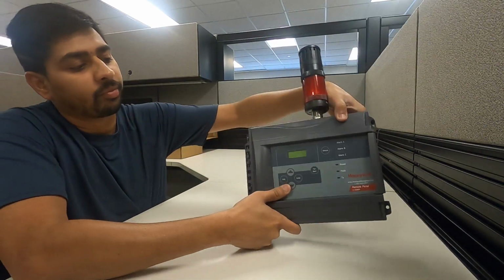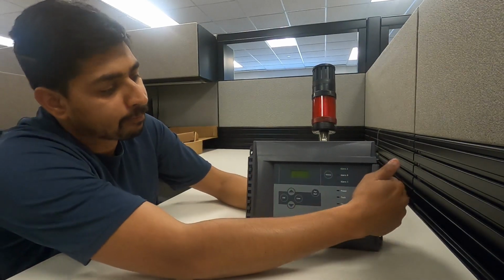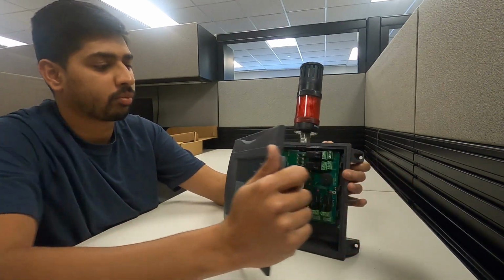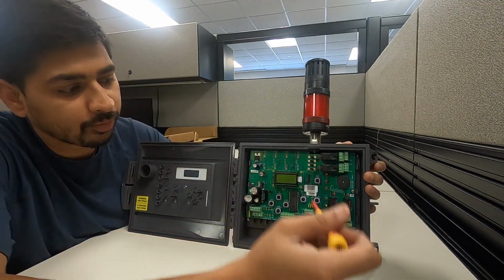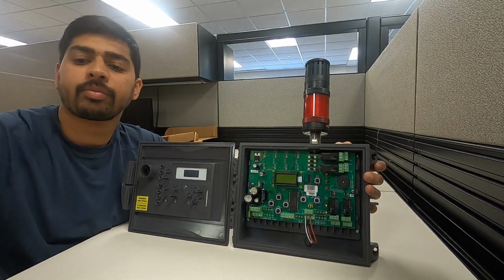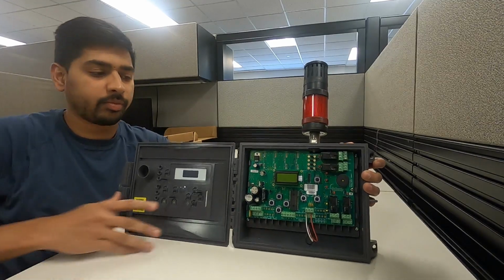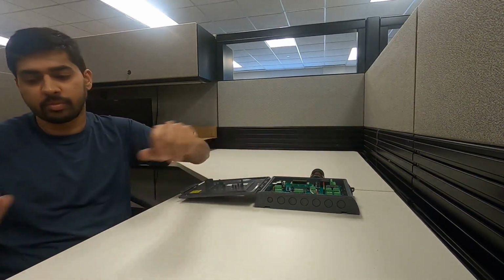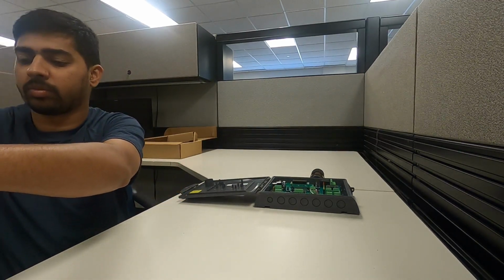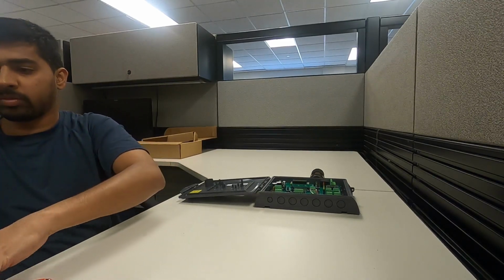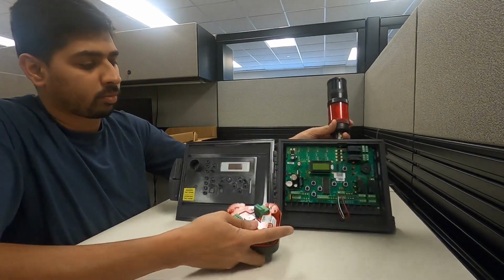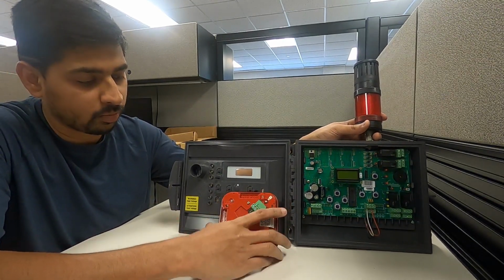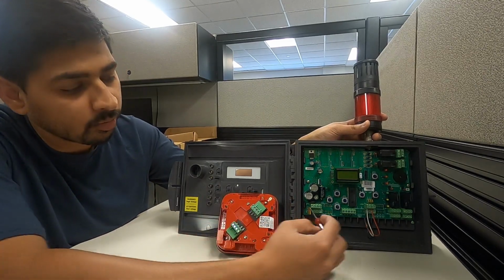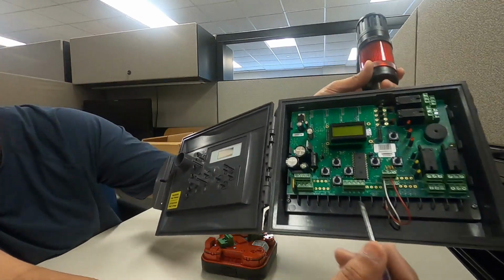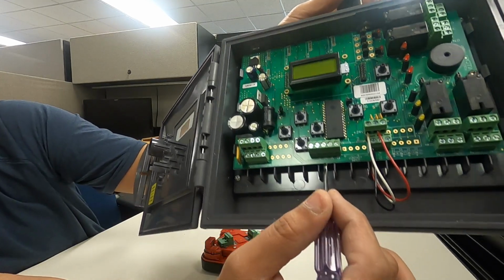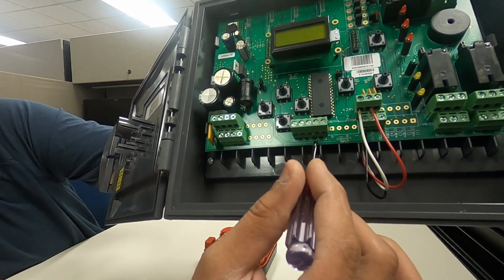So depending on how you want to design the job, or how much you want to spend on this application, you will have to select these sensors, decide where to place them, how you want to wire them, and then get it to your controller to recognize how much concentration you're getting in the garage space. The usual application for these is that whenever there is a spike in the concentration of the gas, the controllers will energize the circulation fans, which bring in fresh air and take out the existing air through the exhaust fans. So that's as simple as that. All these air quality sensors do is maintain a certain level of concentration so that there is always fresh air passing through and it shouldn't create any hazards.